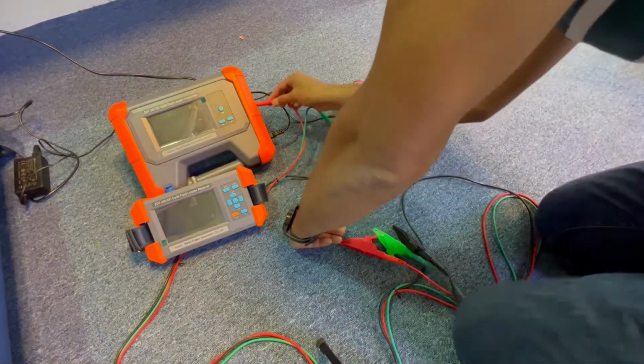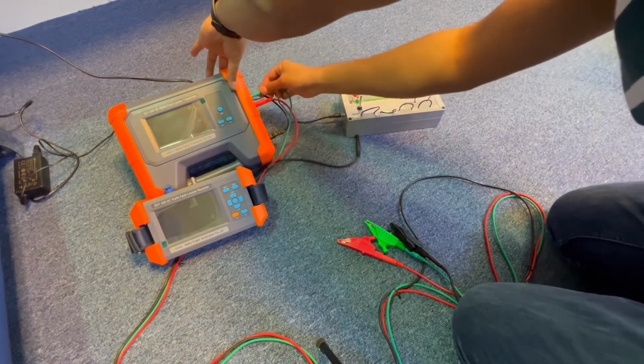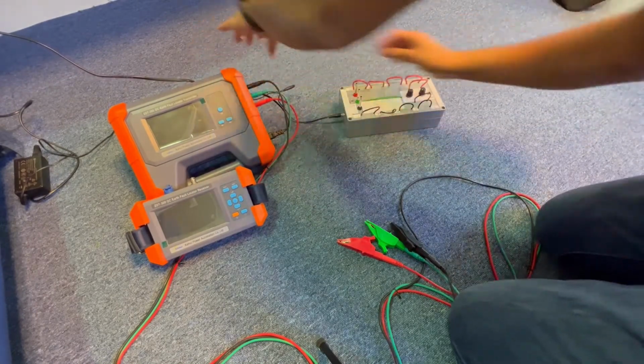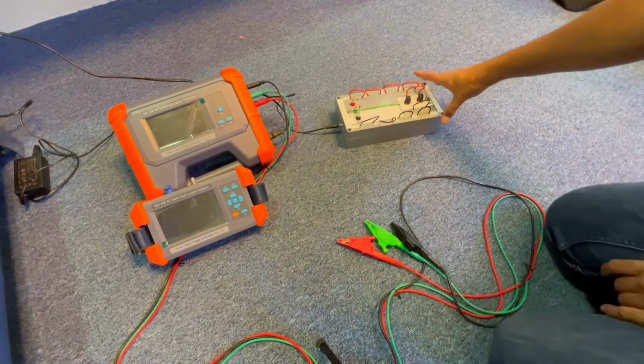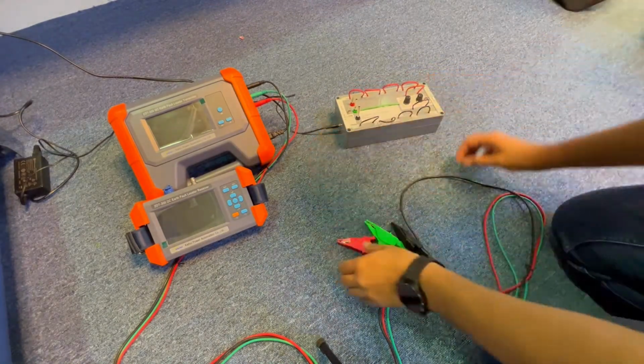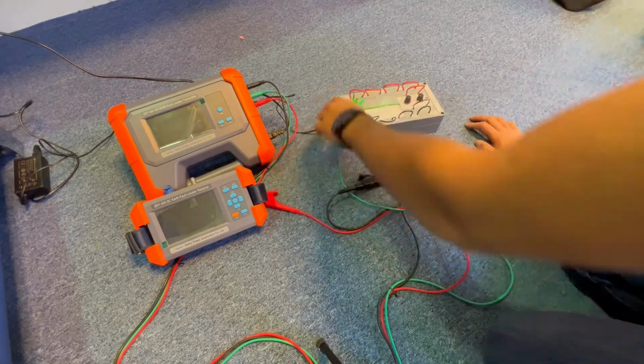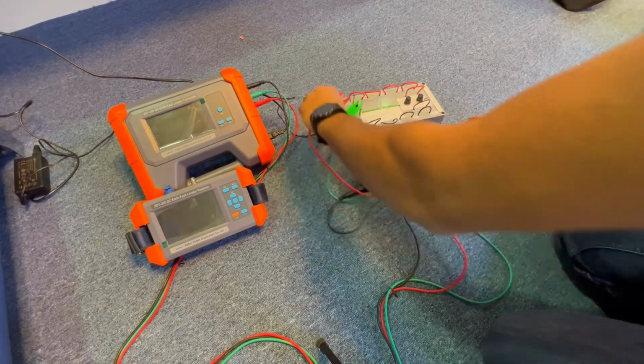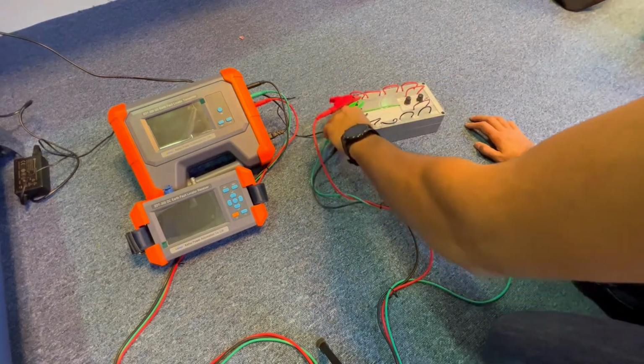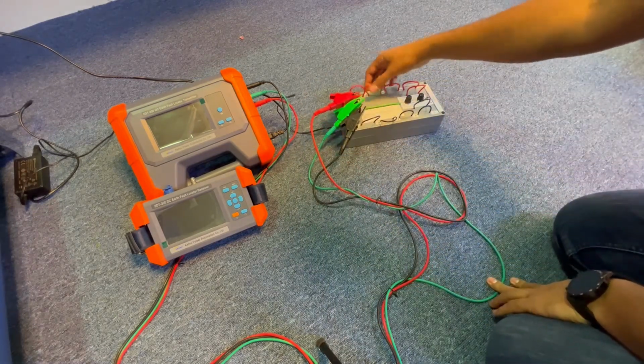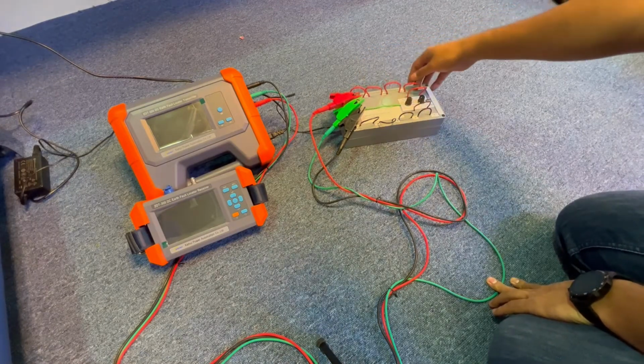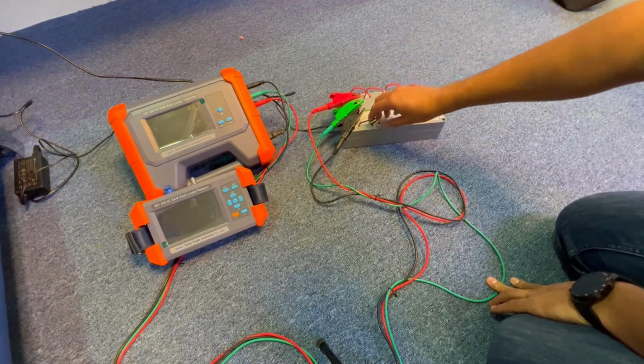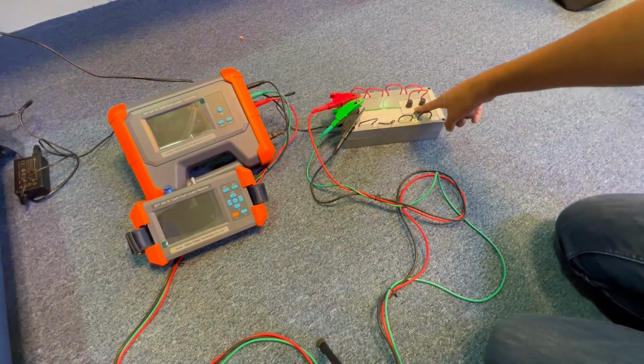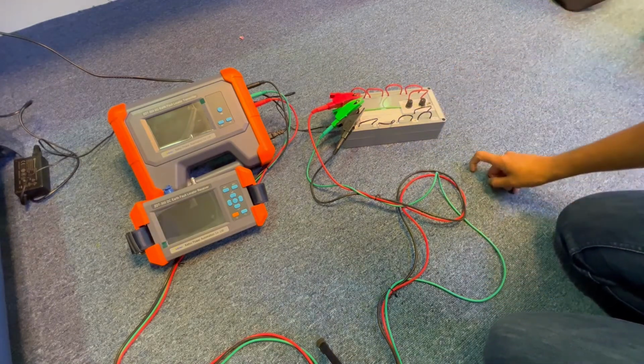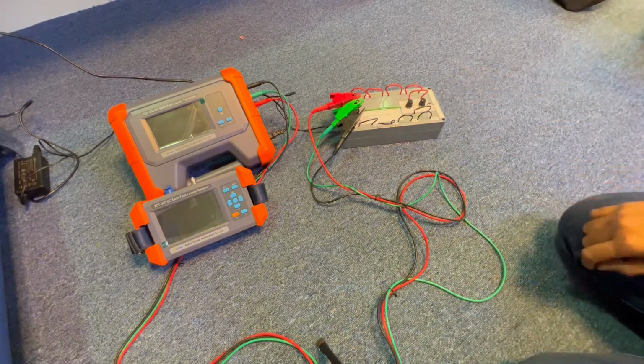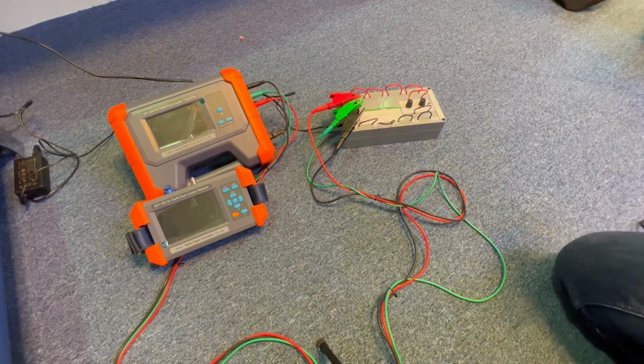Let's do the connection. Red goes to the positive, green goes to the ground, black goes to the negative. Considering this as a 20 volt DC system, we connect green first, always to the ground, then red to the positive, and then black to the negative. You can see that we have some feeders already here, positive feeders in red and negative feeders in black, and we have created a fault of 47 kilo ohm resistance in the positive. So this is a positive fault, and we can see how this shows the fault in positive and negative.